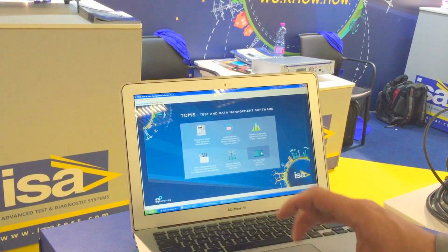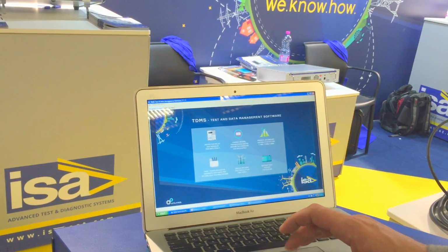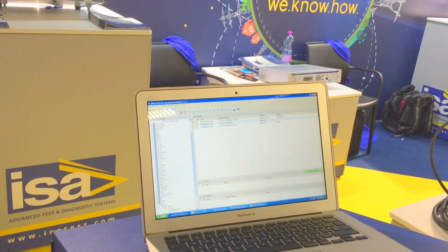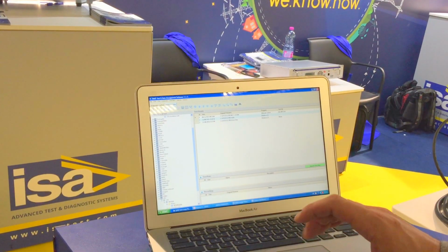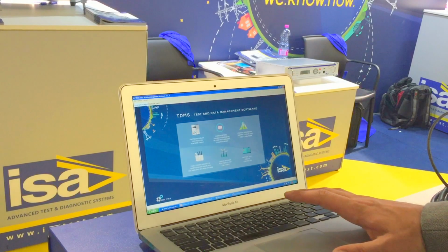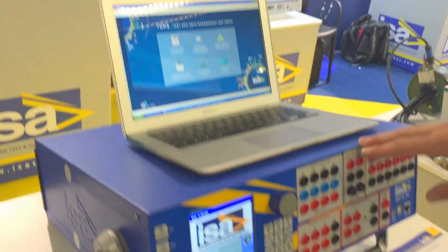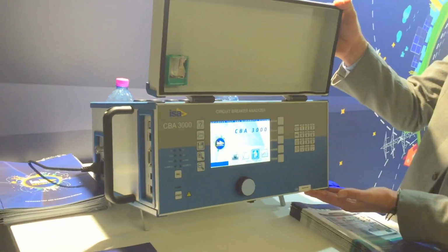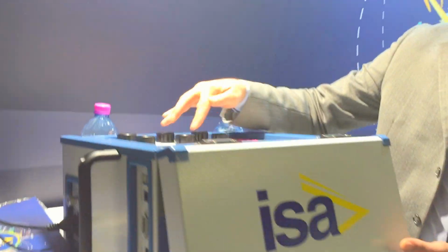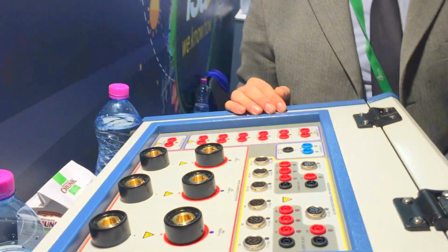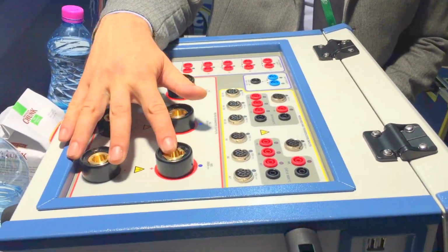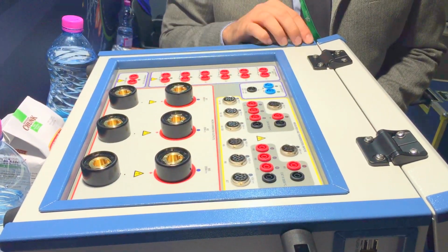So all solutions within one software package, which also can be used to save your results, as actually it will be a database in that case. So that's our secondary injection. Then we move to our circuit breaker analyzer. The newest version is CBA 3000, the first circuit breaker analyzer in the world which has 3 outputs to measure resistance, static or dynamic resistance, up to 200 amps.